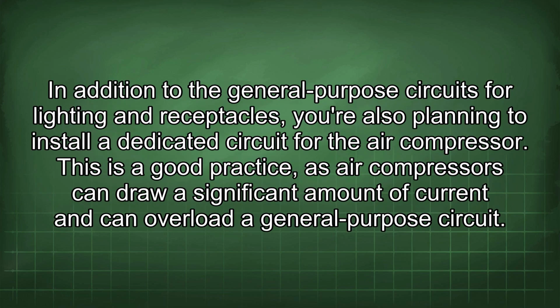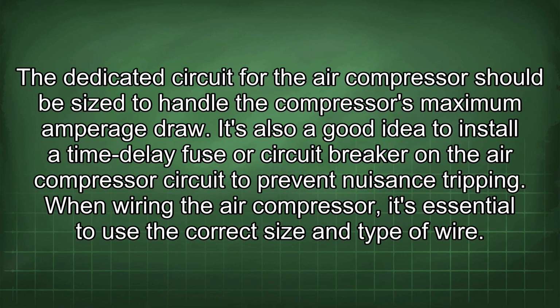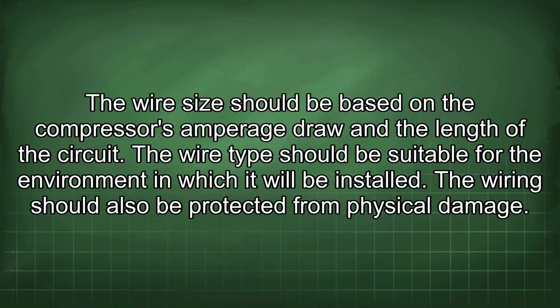In addition to the general-purpose circuits for lighting and receptacles, you're also planning to install a dedicated circuit for the air compressor. This is a good practice, as air compressors can draw a significant amount of current and can overload the general-purpose circuit. The dedicated circuit for the air compressor should be sized to handle the compressor's maximum amperage draw. It's also a good idea to install a time delay fuse or circuit breaker on the air compressor circuit to prevent nuisance tripping. When wiring the air compressor, it's essential to use the correct size and type of wire. The wire size should be based on the compressor's amperage draw and the length of the circuit. The wire type should be suitable for the environment in which it will be installed. The wiring should also be protected from physical damage.